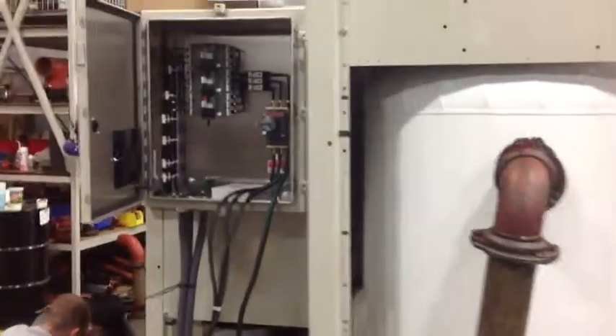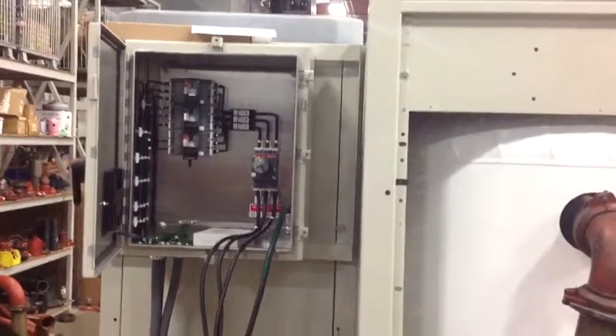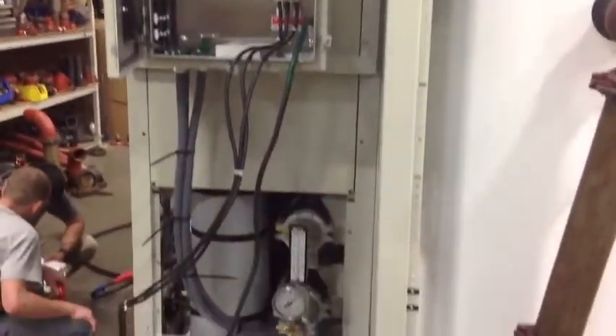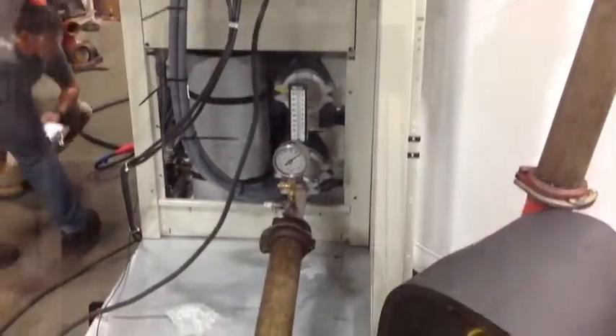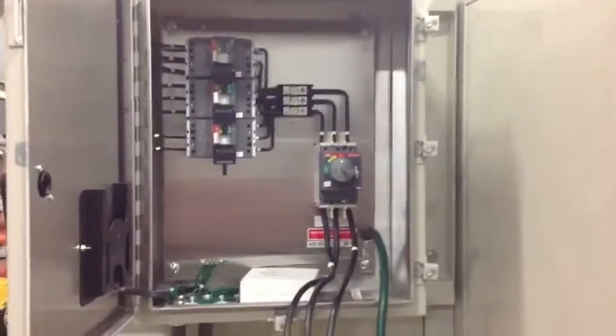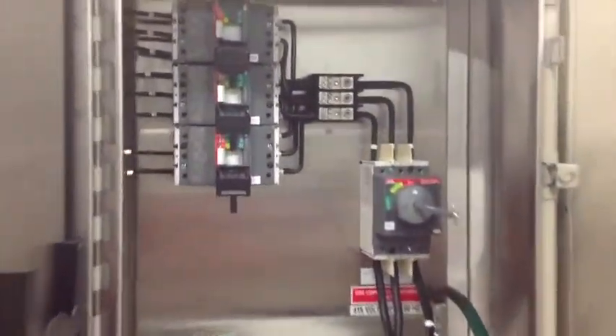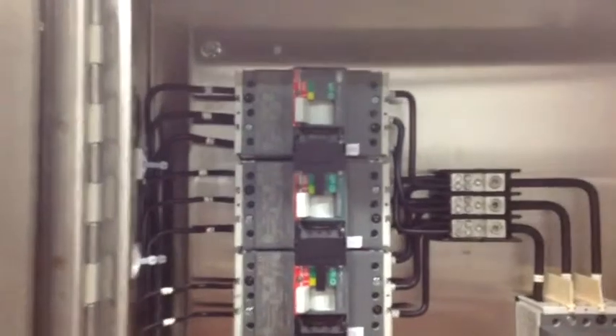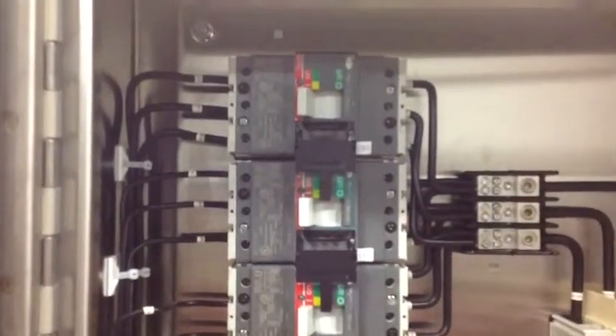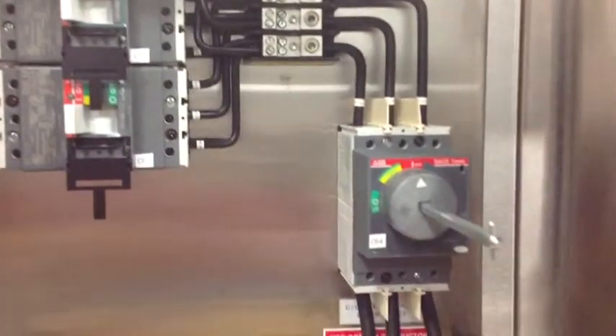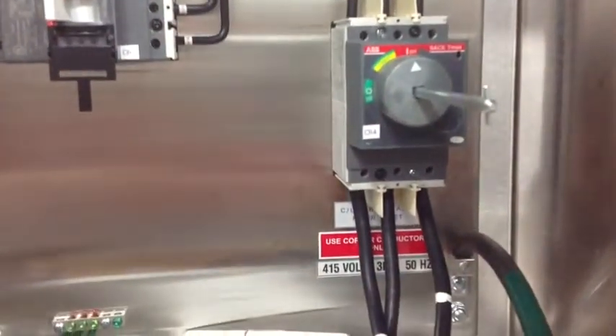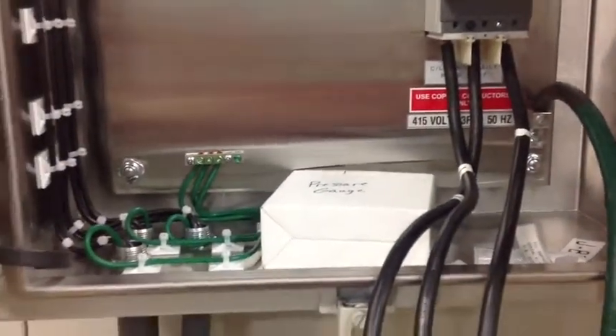Now we'll pan left to see the single point power junction box. On the right hand side you'll see the door interlock disconnect switch heading up to the power distribution block, and then over to the 3 circuit breakers. 1 for the mechanical module, 1 for the C1 panel that connects to the remote panel, and 1 for the pump module. That is the single point power door interlock disconnect switch where power is brought to the entire chiller package.